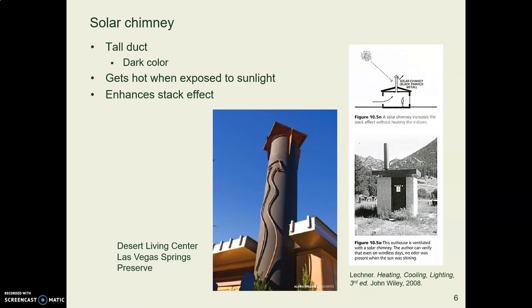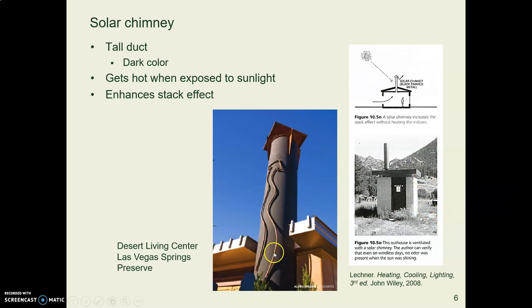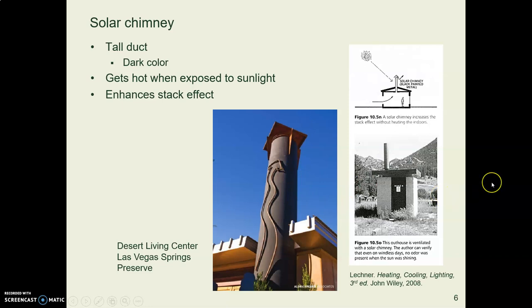Surprisingly, if you paint a stack or tube a dark color like black, you actually get more cooling — which you might think is the opposite. But here's how it works: black, having low albedo, absorbs a lot of solar radiation. As the stack heats up, the air inside is warmer, it rises through the stack, and that creates more suction below, actually pulling more air through.